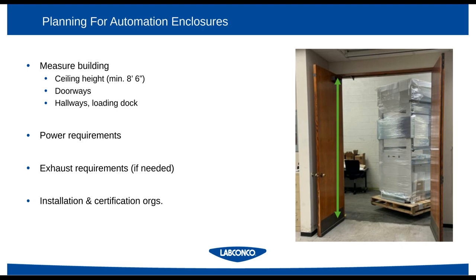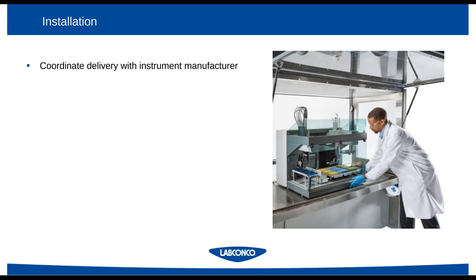And what this means is that when the system is purchased, the automation enclosure should be put into place first and certified empty to make sure that it's operating correctly, and then again evaluated by the certifier after the instruments that are going to be placed inside of it are set. And that's to ensure not only that the enclosure was operating safely first, but secondarily to make sure that the instrument that's being placed inside is properly functioning and not disrupting airflow significantly.